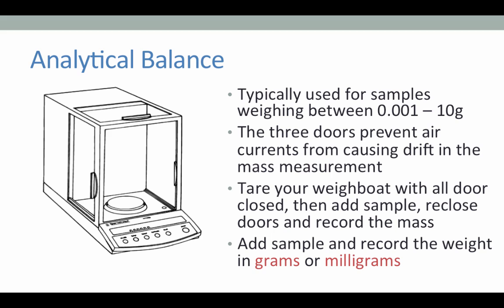So when using an analytical balance, first place your weigh boat inside the weigh chamber, close all three doors, and press the tare button and wait for the instrument to display 0 in every decimal. Once the instrument is zeroed, open the door, add your sample to your weigh boat, close the door, and wait for the reading on the digital display to settle. Record the mass of your sample, including every decimal place displayed.